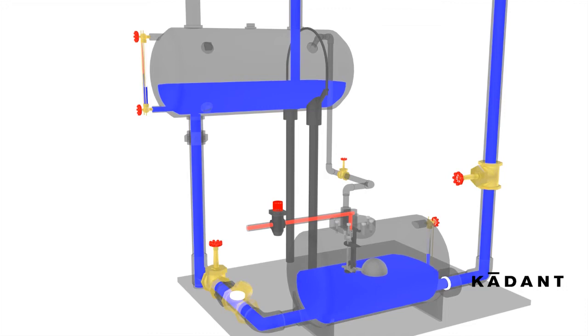When the condensate reaches the lower level, the float mechanism resets. Residual motive pressure flows into the receiver. Once the pump tank and receiver pressures equalize, the cycle will repeat.